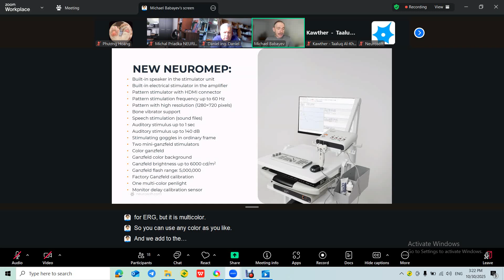Now we will make a factory Ganzfeld calibration. Each Ganzfeld will be calibrated in our factory, and parameters of this calibration will be saved inside the Ganzfeld. So it is not necessary for you to think about calibration. You can change the Ganzfeld and it will have the same stimulus intensity. Previously, in the device, we had 4 pen lights with different colors. Now it is only one pen light for ERG, but it is multicolor, so you can use any color as you like. And we add to the delivery a monitor delay calibration sensor.